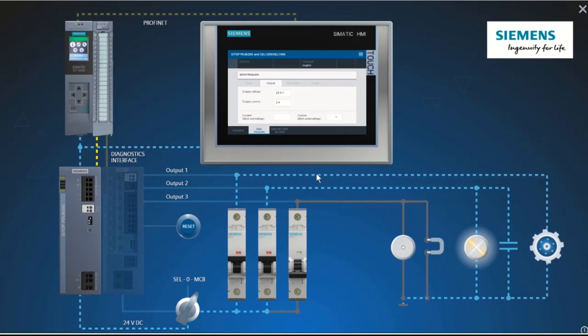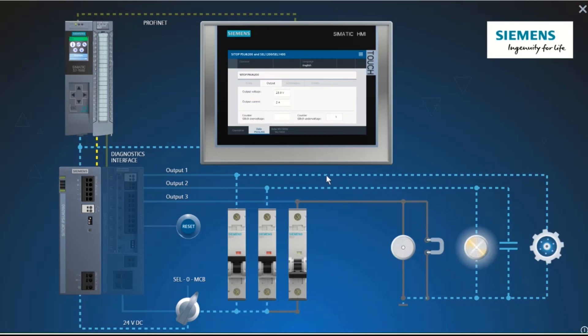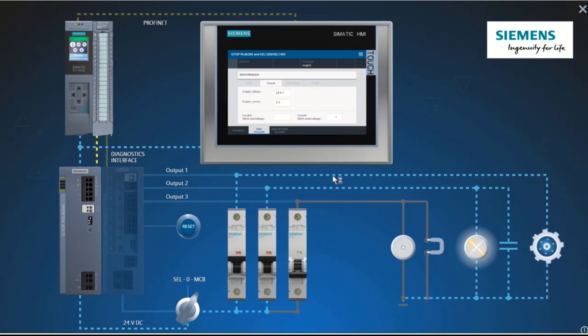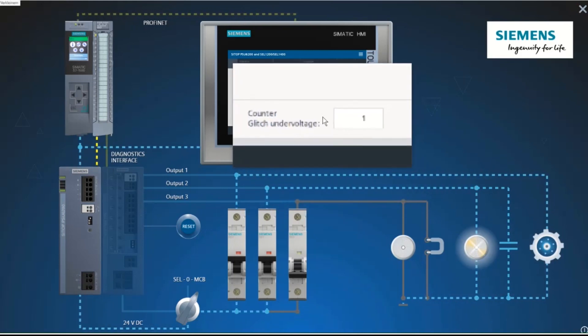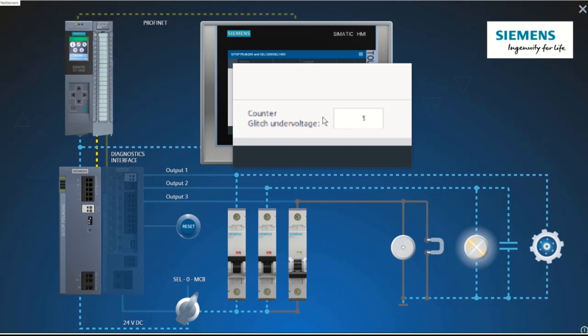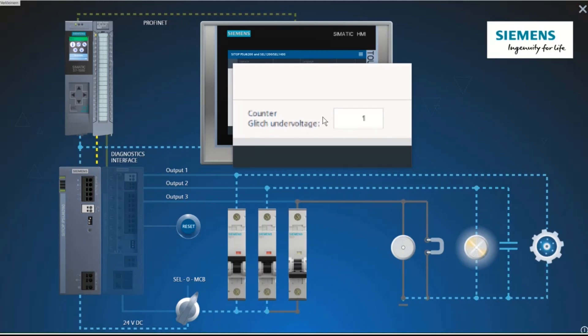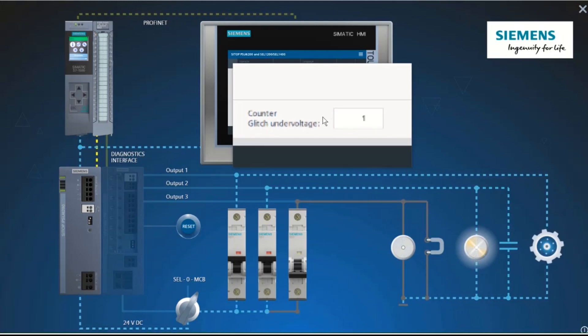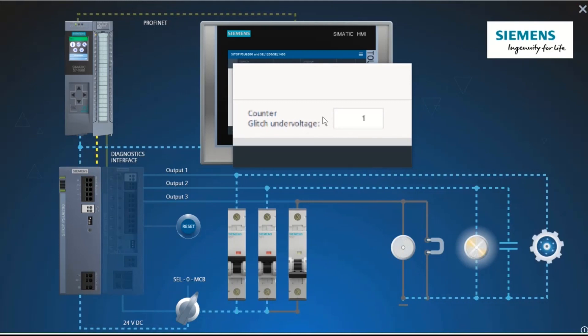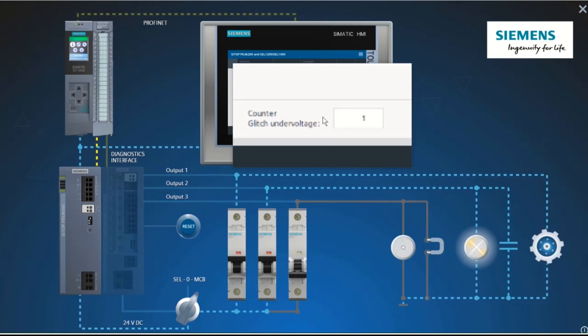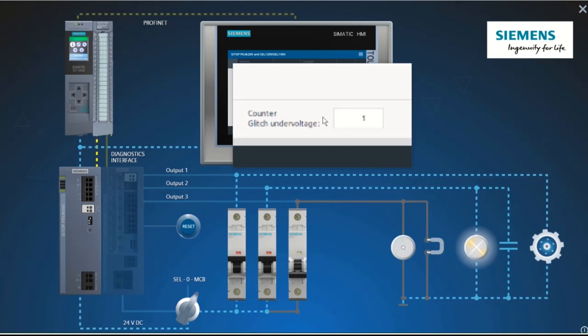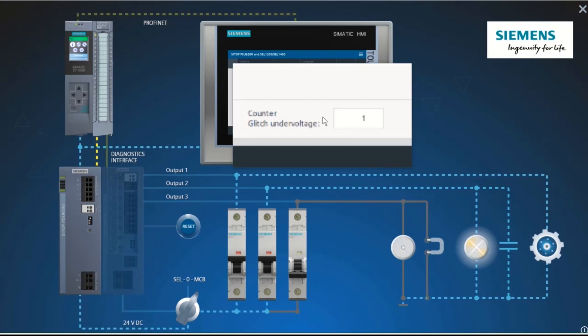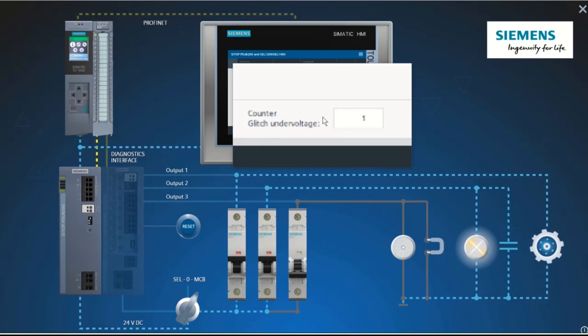Let's have a look at the faceplate of the PSU 6200. The glitch under voltage counter indicates 1. This means the user can see where the PLC has crashed. The voltage drop was registered by the SITOP PSU 6200 and transmitted to the PLC after restarting.